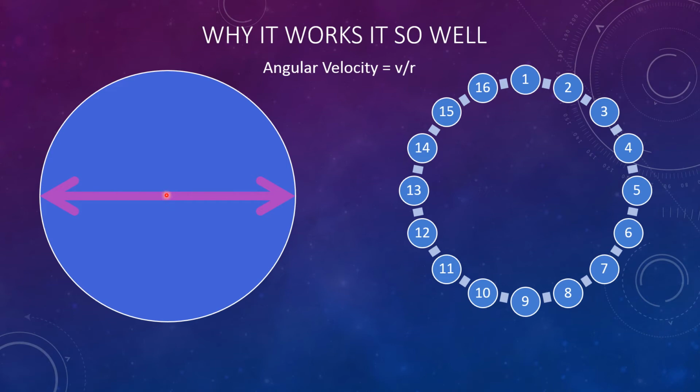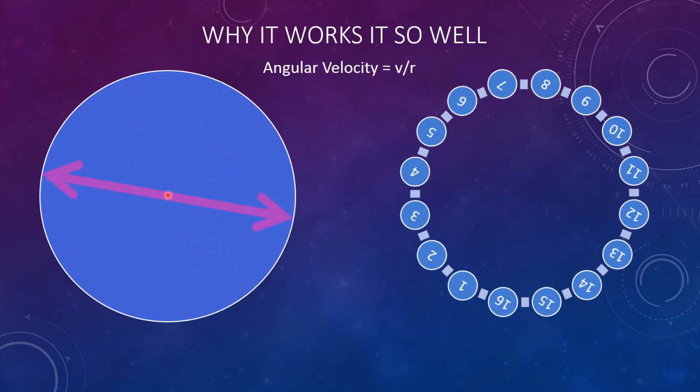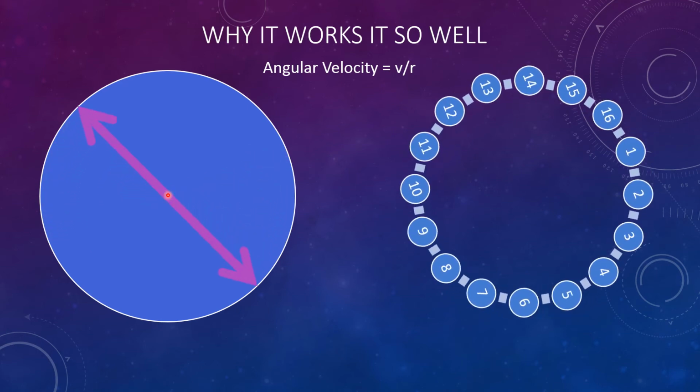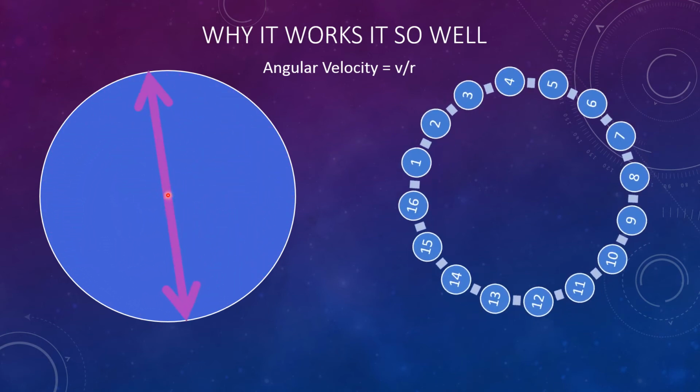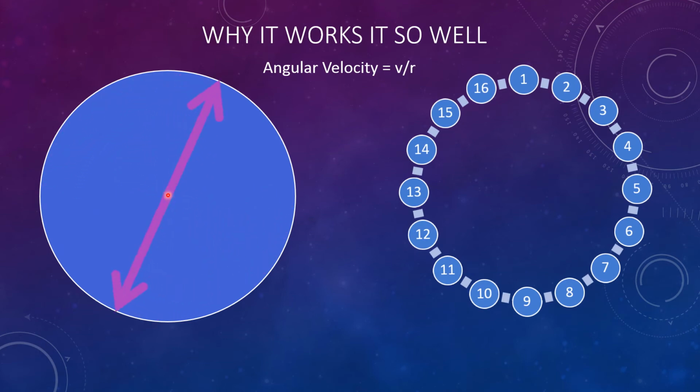So you can see that it's fast, but it's not very fast rotation. Now, we thought about, well, how do we get faster rotation in the same footprint? What do we do in this footprint to get that faster rotation? Well, what if we went to smaller, somehow combined or manifolded separators? So if we look at the same situation, what does decreasing the radius do for me? Think again about our ice skater. Now the radius is from here to here, so that's just like the ice skater pulling their arms in and they rotate faster.